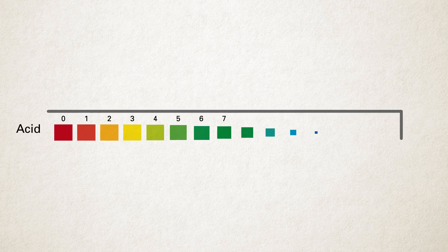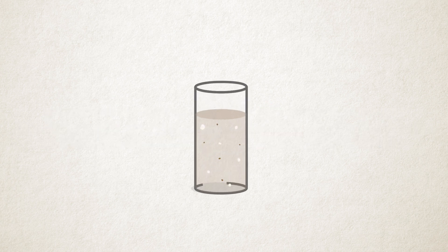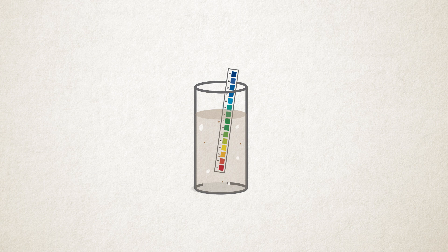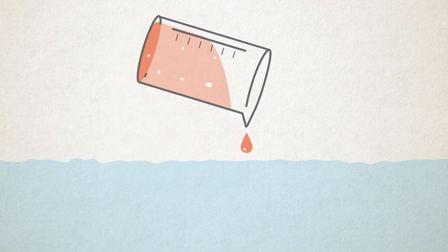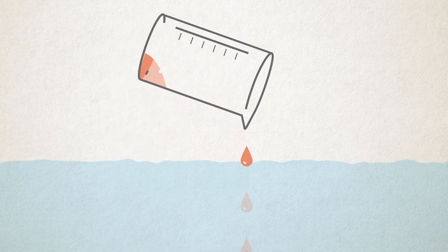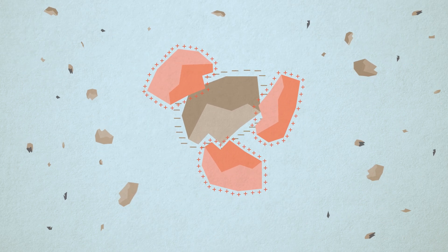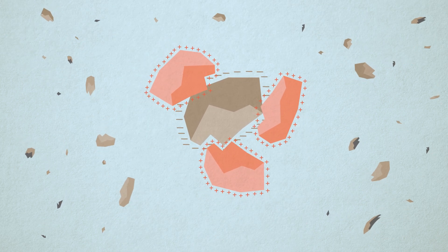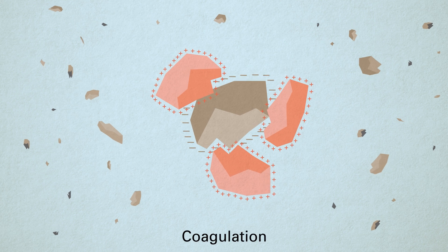Firstly, we raise the pH level of the water by using a hydroxide such as lime. This prepares the water for the chemical reaction in the next steps. Then we disrupt the negative charge of the colloids by adding a coagulant. The coagulant has a positive charge which neutralizes the negative charge of the colloids. This is coagulation.